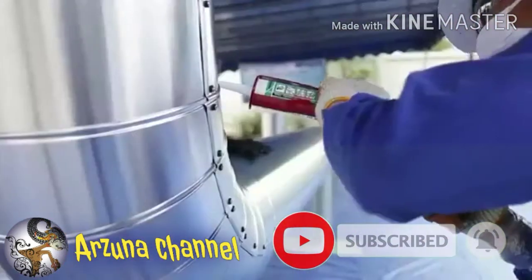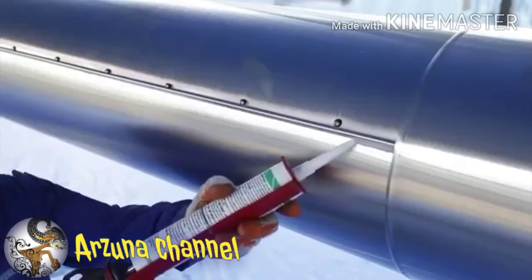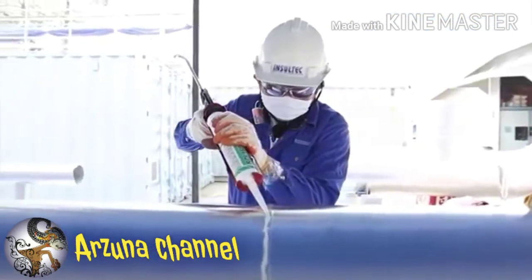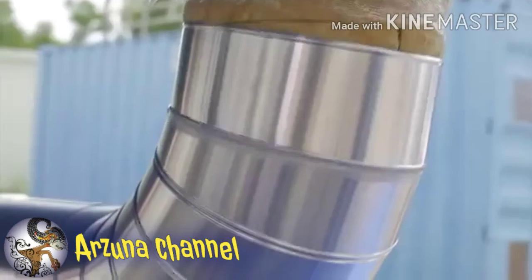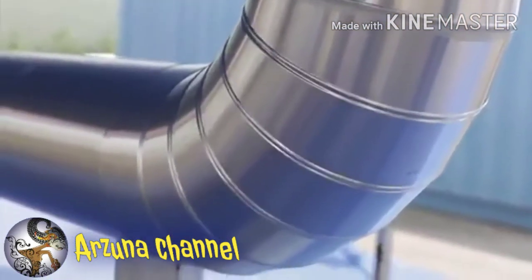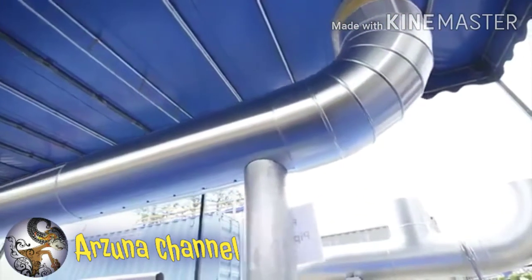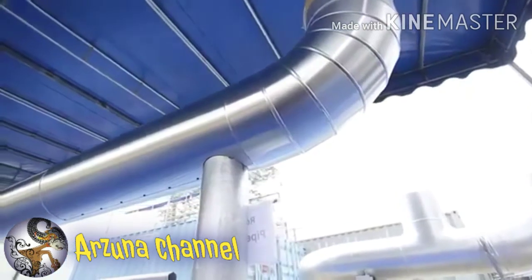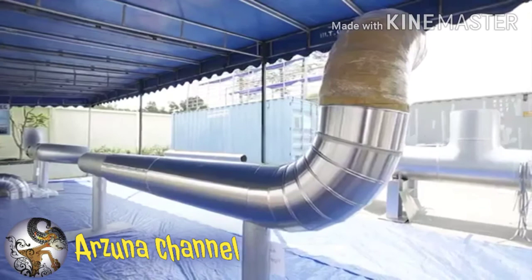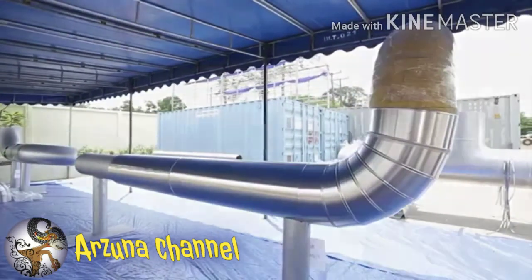To prevent water and moisture ingress in the insulation material, all seams and joints can be sealed with silicone glue as per industry standard. If the installation is stopped during the day for a few hours, proper precautions should be taken on the installed Rockwool pipe section products to prevent ingress of moisture, water, and rain by wrapping the insulation with plastic film. However, the installers need to be aware that they should install Rockwool insulation products only as much as they can clad per day.